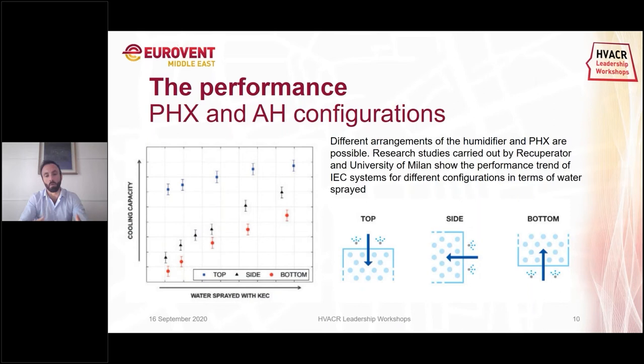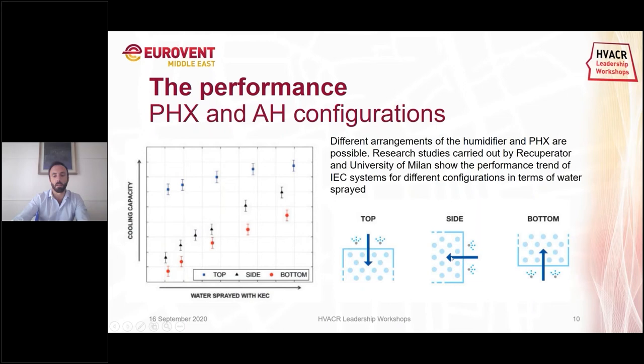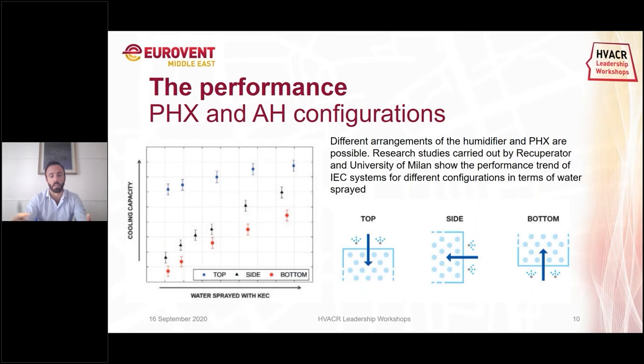This is because it is really important that water enters inside the heat exchanger — in that way we work closer to the wet bulb temperature at each step, as the air inside the exchanger heats up and is then cooled and humidified in the next step, keeping us closer to the saturation curve. With the side and bottom configurations, gravity compromises the water flow inside the exchanger and we lose a lot of cooling capacity. The exchanger in these configurations works like a water droplet separator because of its internal geometry. This shows how important the configuration and internal humidification of the heat exchanger are.